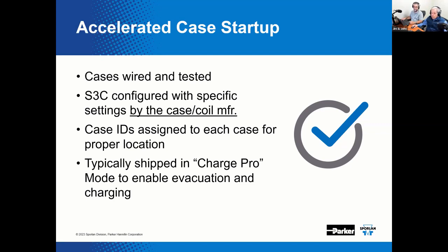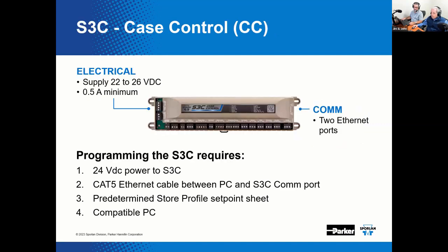If the case is wired and powered up, something called charge pro mode, which is part of the control scheme of the S3C, will force the step motor valves to 100% open and will also open the liquid line solenoid valve, including the circuit EEPR, if there is one there. Think that might help with charging the system? It could. Yep. Everything wide open, it should charge rather easily.